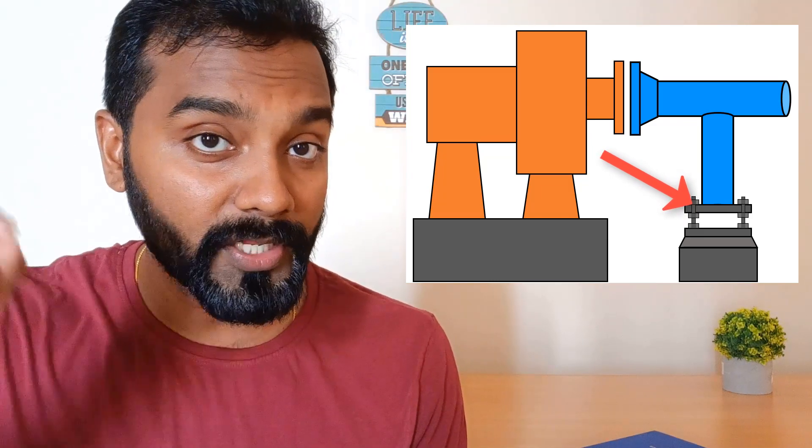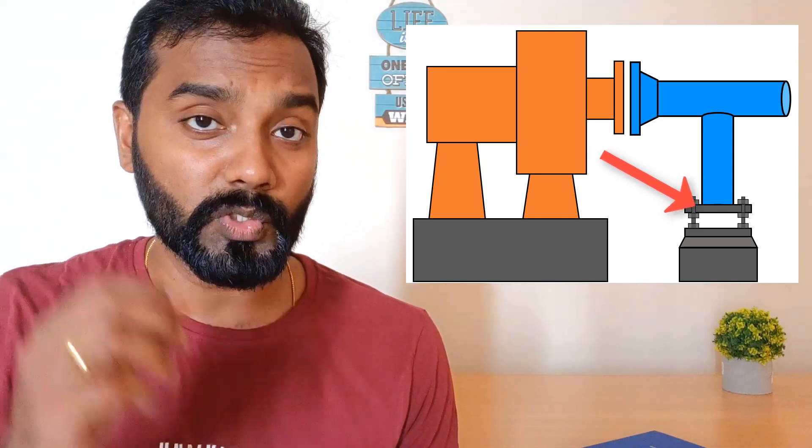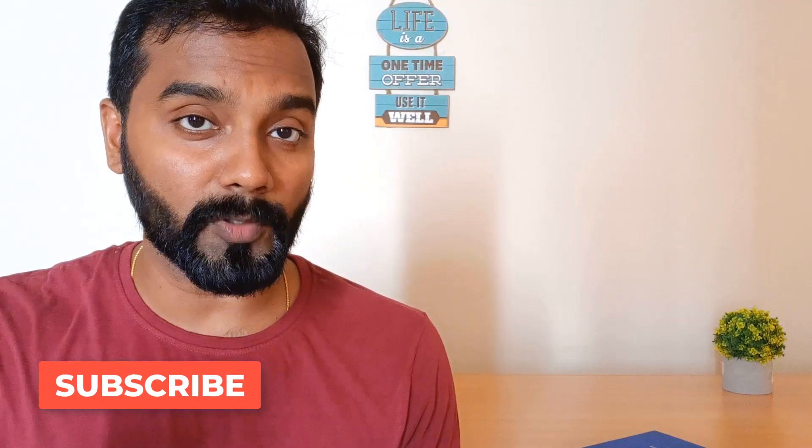It is really important for the pump to be free of frictional forces, additional loads, and machine misalignment. This is one of the key reasons why adjustable supports are provided as the first support at the pump suction. Once the pump is installed, you can always adjust the elevation of the piping according to the pump nozzle. If you do not provide adjustable supports, you will have misalignment, and loads will be transferred to the pump nozzle unknowingly. With adjustable supports, you can fine-tune the adjustment so that no loads are transferred to the pump suction.